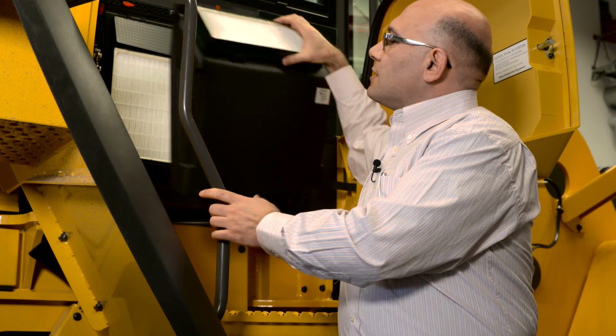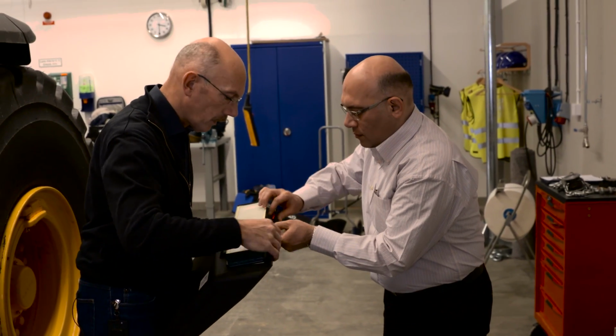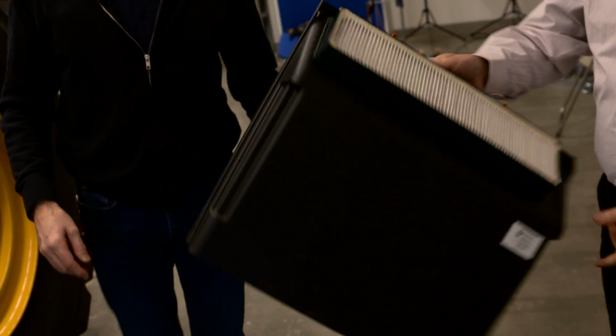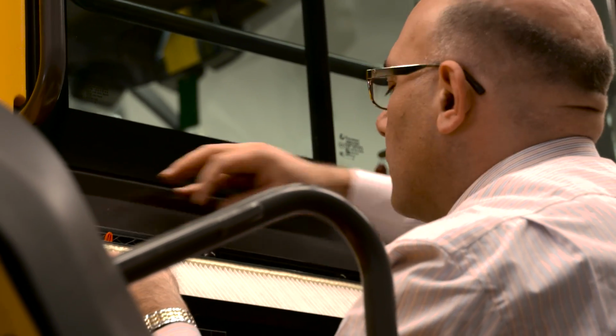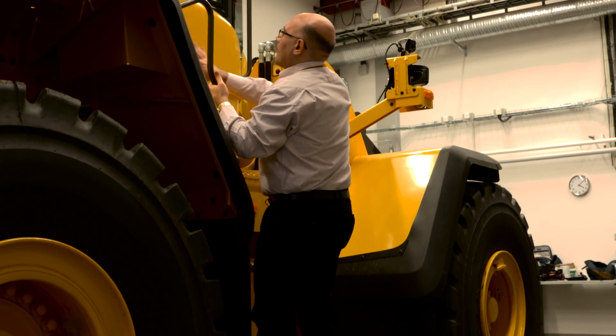Years ago, we got some product maintenance issues from one of our customers regarding the malfunction of the AC system, the air conditioning system, and the compressor. And when our technical team did a deep investigation on this, we found that both the pre-filters and the main filter were completely clogged. I can show you here, this is our filter unit. A clogged filter means no air passing through the heat exchanger and the evaporator. In this particular case, it caused heat to build up and total system failure. And we saw that the customer paid a lot of money because of the malfunction of the system, the cost of changing parts of the air conditioning system, and of course, the downtime of the machine and the whole system.